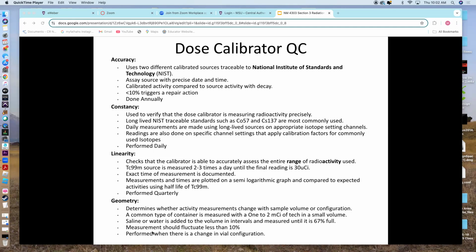So like I said, most of the time when your dose calibrators were set up, they were probably set up to look at 3 milliliter vials, and probably maybe 5s. A good example of this is at my facility, and this is when I was working more in general nukes, but we do a treatment called TheraSphere. Maybe some of you have seen some of those. When we initially started doing TheraSpheres, TheraSpheres come in kind of a short, stubby vial.